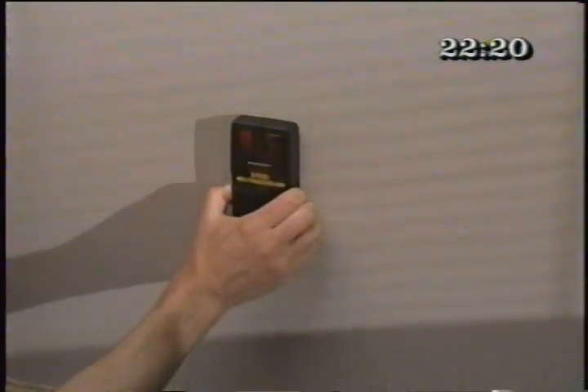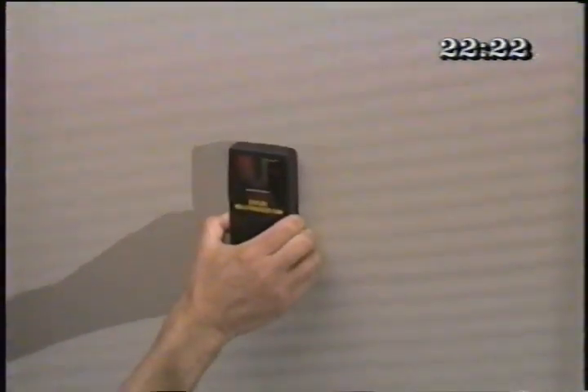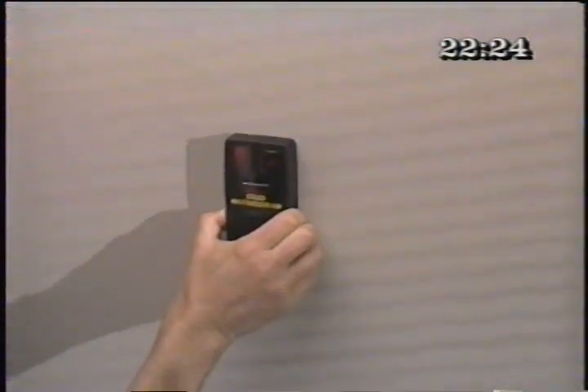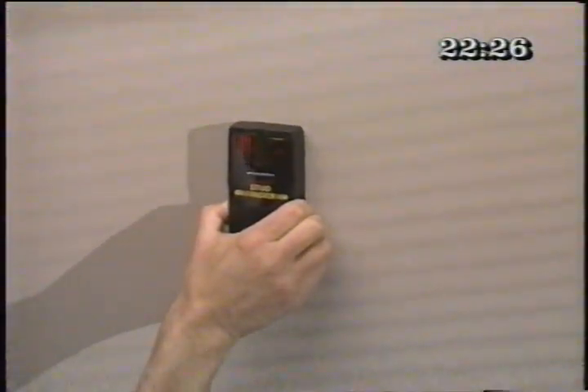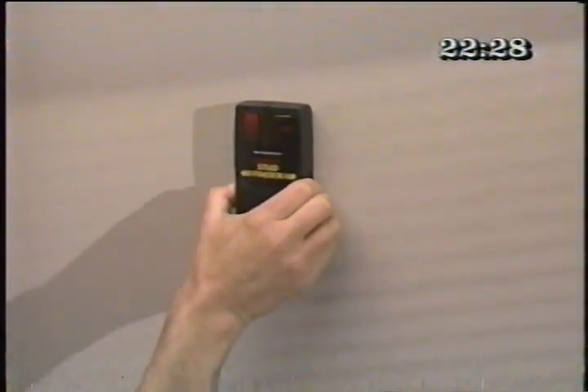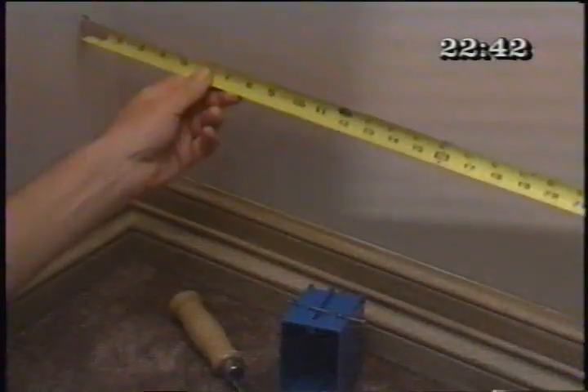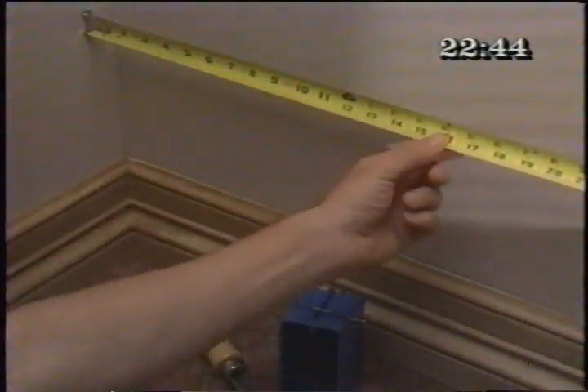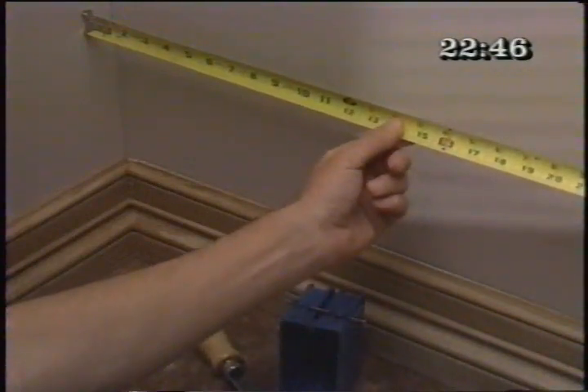If you plan to run the wire down the inside of the wall from an attic, it's a good idea to check above the place where you want the new outlet for an interior wall support called a fire block. A fire block is a short piece of 2x4 that connects two studs, and it obstructs the wire as it's run down the wall. If you locate one above the position you chose earlier, just move the jack to the other side of the same stud. Once you locate the stud where you want the box, measure the distance from the closest corner of the room.